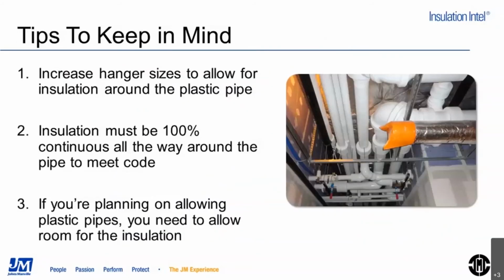So now when you guys are designing the piping systems, you need to treat these systems like they're chilled water. Everything has to be on the outside of the insulation. Everything: hangers, all of it. Saddles have got to be on the outside. Nothing can be on the inside of the covering, like the hangers. So everything has to be external, 100% all the way down. But it can be done, so no problem.